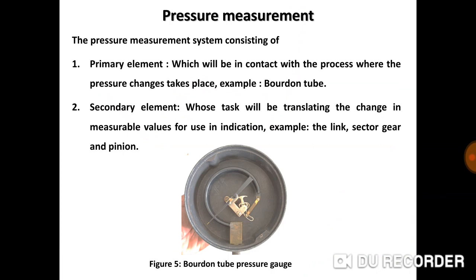Pressure measurement. The pressure measurement system consists of primary element and secondary element. From the Bourdon tube pressure gauge as an example, the primary element is Bourdon tube pressure gauge which will be in contact with the process where the pressure change takes place. However, the link, sector gear, and pinion of Bourdon tube pressure gauge acts as secondary element. The secondary element's task is translating the change in measurable values for use in indication.